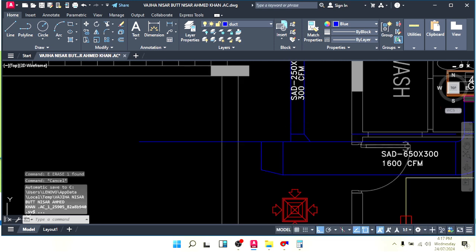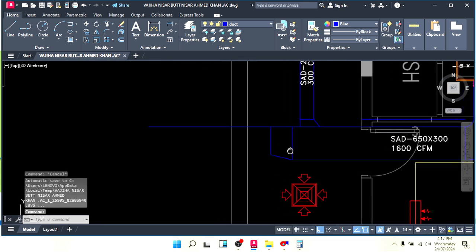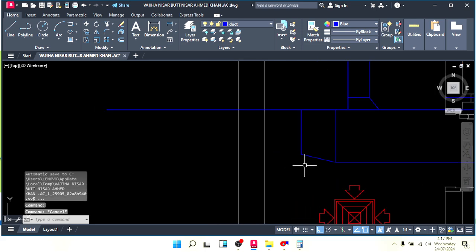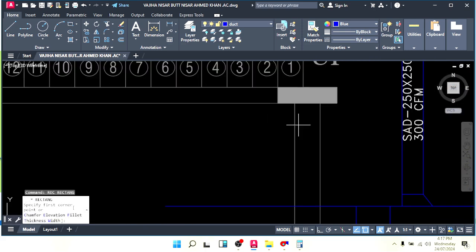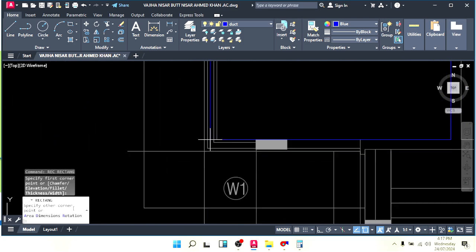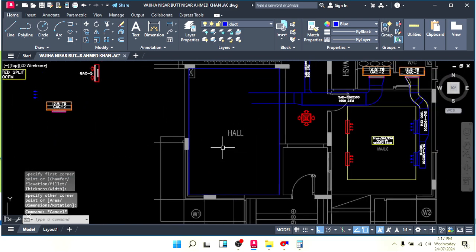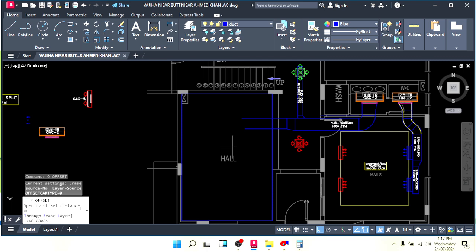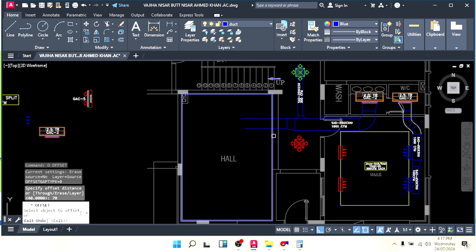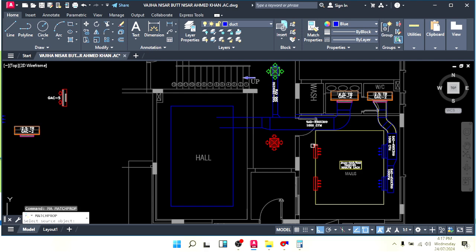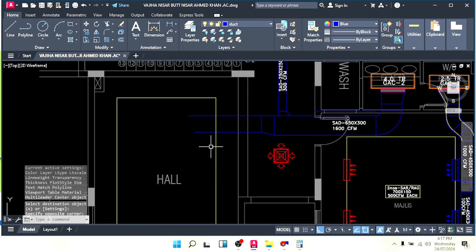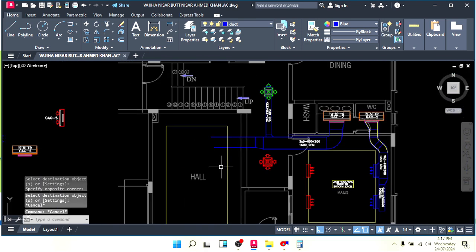I mean the branch is there, so I will reduce the duct on the opposite side. Okay, like this. Now we need a bulkhead here also. Here also make it, 70 centimeter is enough. Bulkhead, this is our recommendation. The interior company will see how much they require, but the minimum is 70. They have to follow this one.